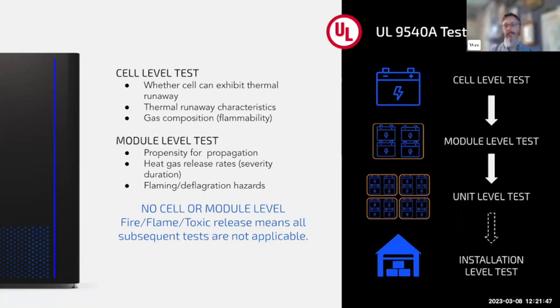Then unit level is when you take those batteries and put them in the enclosure, which is this photo on the left. Ultimately there's the installation level, which would be like the electrical room or the shipping container. Because ours is fundamentally safe at the cell and module level, there's no need to do a unit level or installation level test, whereas other chemistries have to put in elaborate and expensive fire mitigation.